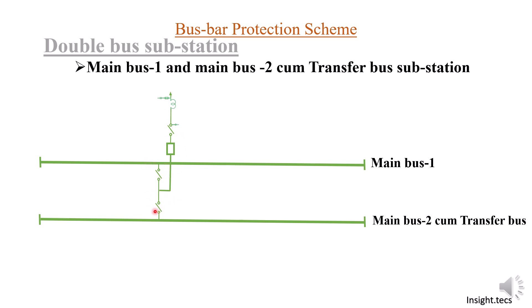As usual, a feeder has two selector isolators — it is connected either to bus one or to bus two. A special feature added is a separate isolator that connects the two buses to the equipment separately. This kind of arrangement makes it a main bus two cum transfer bus, so main bus two also plays the role of a transfer bus as and when required.